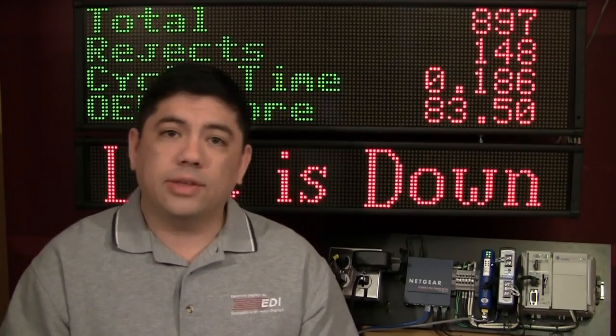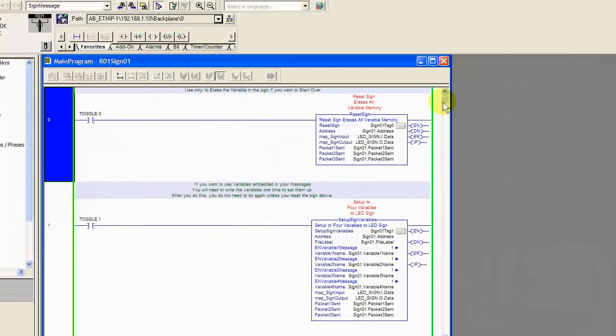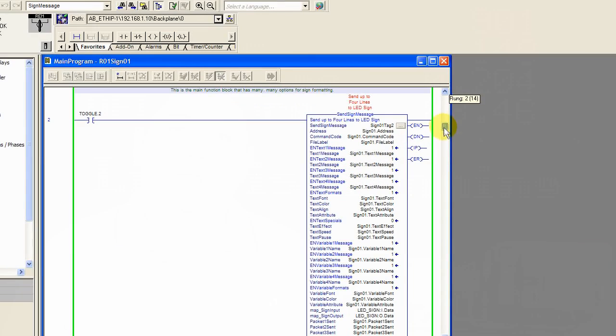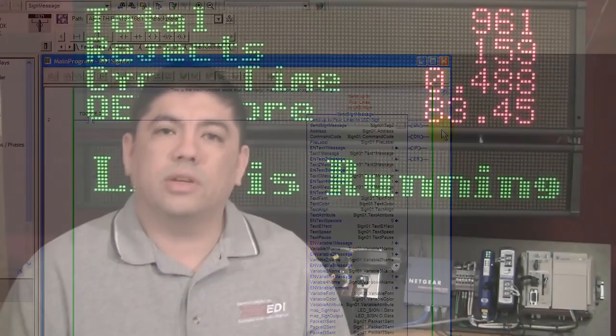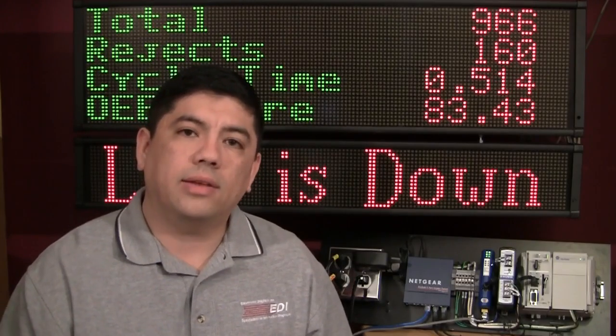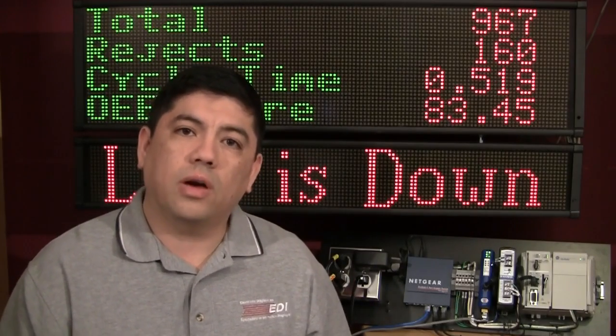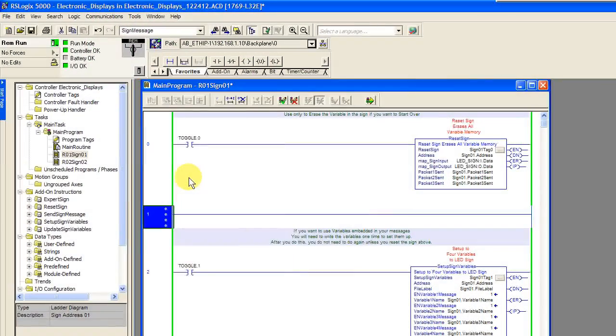What we've done is added some easy drag-and-drop functional blocks that will easily integrate with RSLogix 5000 software. Since about version 16, Allen-Bradley has given third-party vendors a way to add instruction blocks — what they call add-on instructions, or AOIs — to their software package, which allows vendors like us to design turnkey function blocks to communicate with our own products.